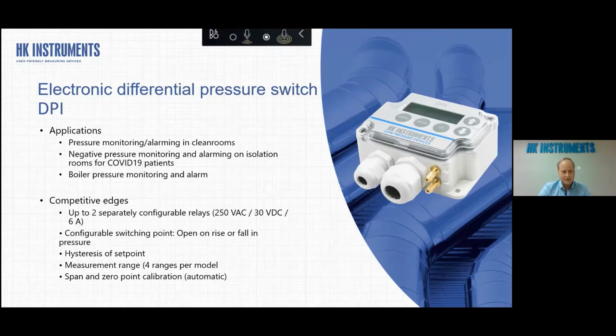And what you have there, in addition to 0 to 10 voltage output, you have up to 2 separately configurable relays. And you can use those up to 6 amperes, so you can basically control a device without any contactor there. And you can freely configure the switching point with 1 Pascal resolution for both relays, and you can choose the direction, if it's open on rise or fall in pressure. And also you can set the hysteresis. So basically you can do very precise settings for the relays.